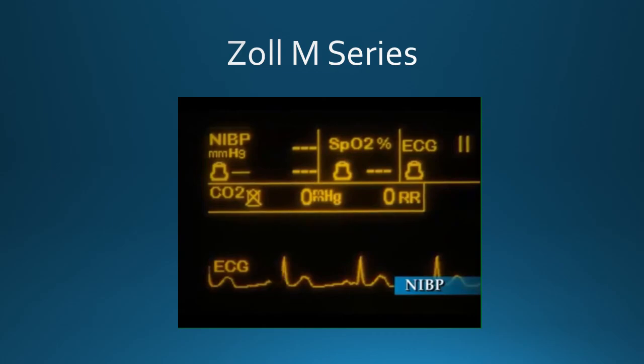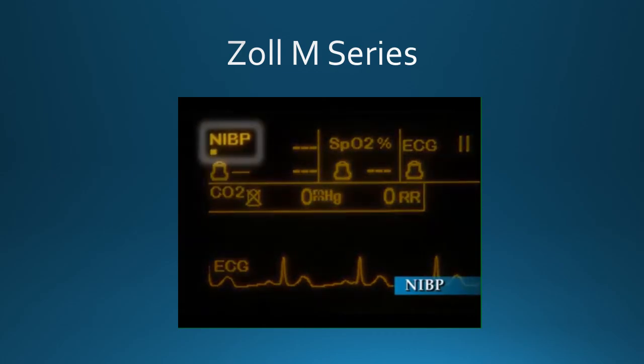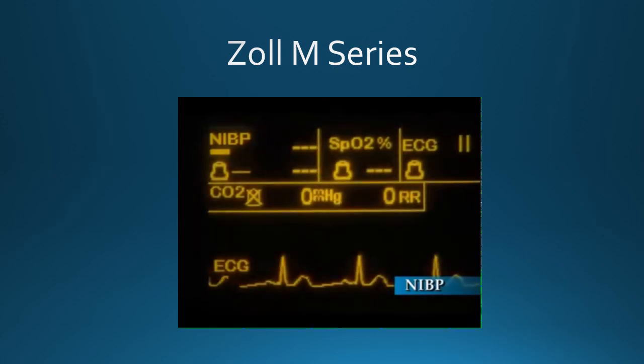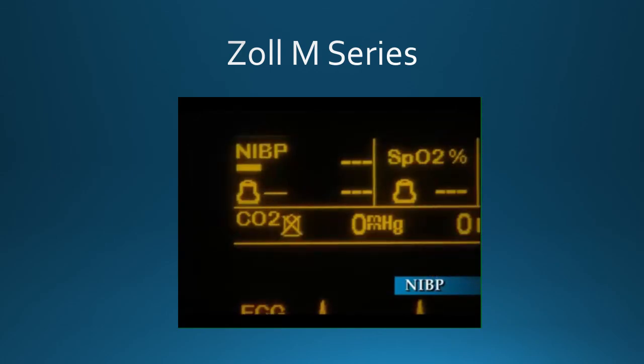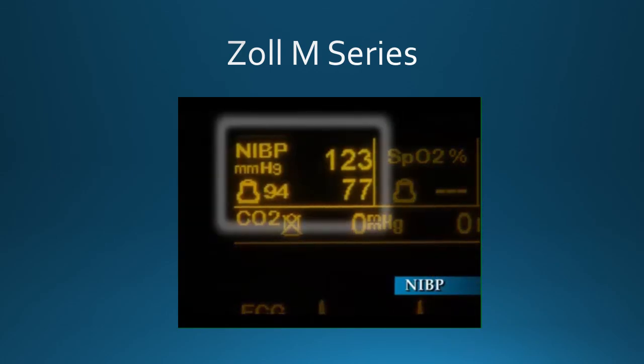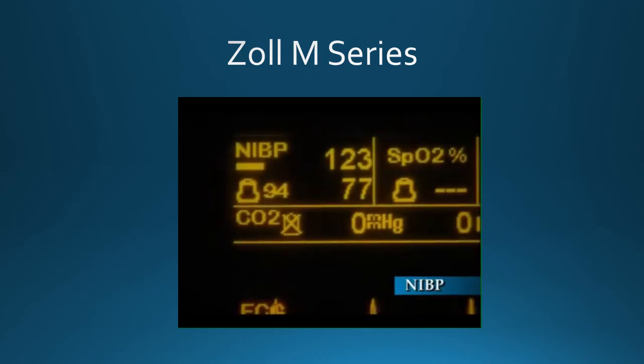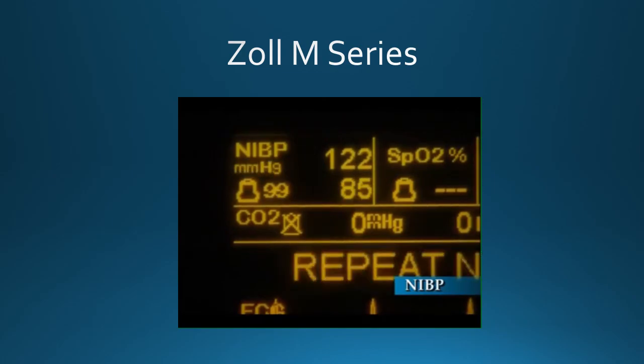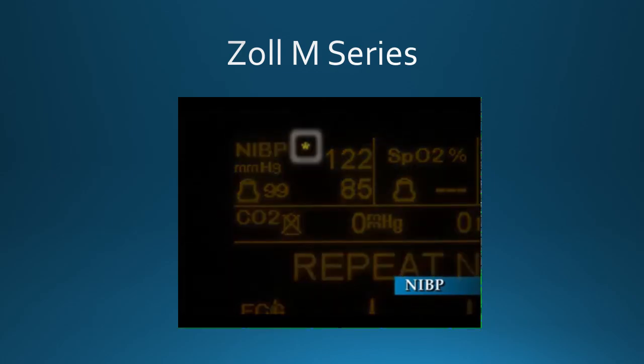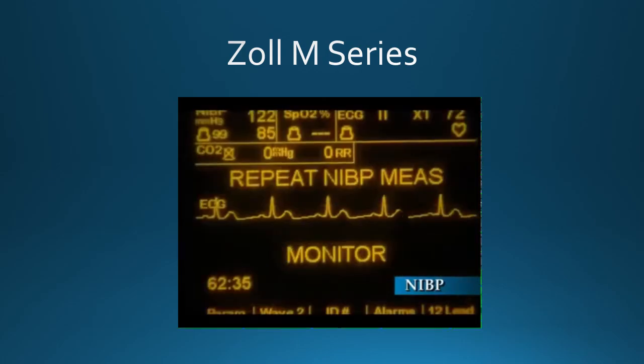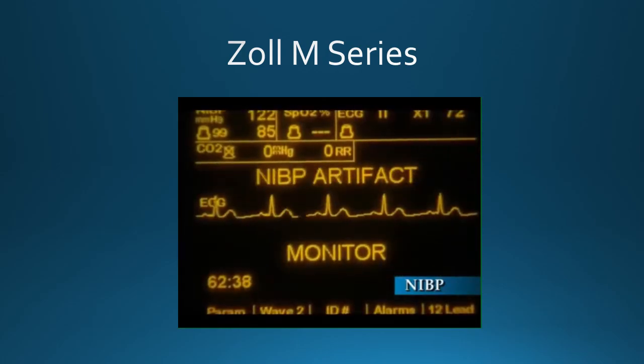If a systolic pressure cannot be detected, the M-Series immediately increases the cuff inflation pressure and completes the measurement. If after 180 seconds the M-Series has not been able to determine systolic, diastolic, or mean pressure, it aborts the measurement and deflates the cuff. After each measurement, the NIBP display area displays systolic, diastolic, and mean blood pressure values. If the M-Series is unable to detect a measurement due to excessive motion or vibration, an asterisk is displayed and the message Repeat NIBP Measurement will alternate with NIBP Artifact.